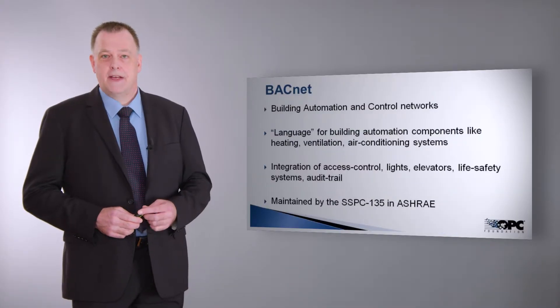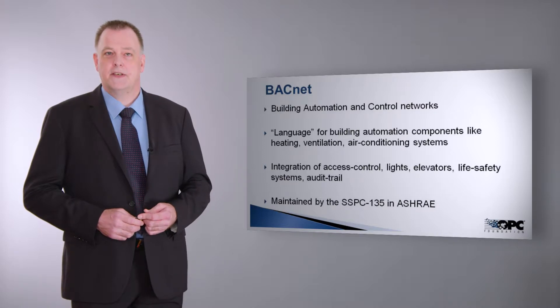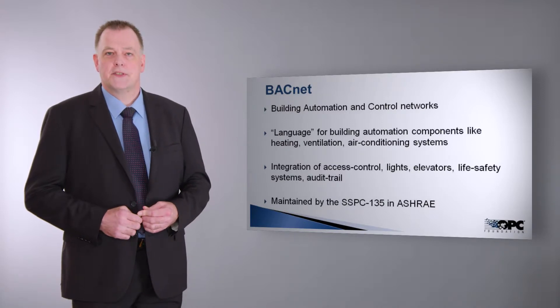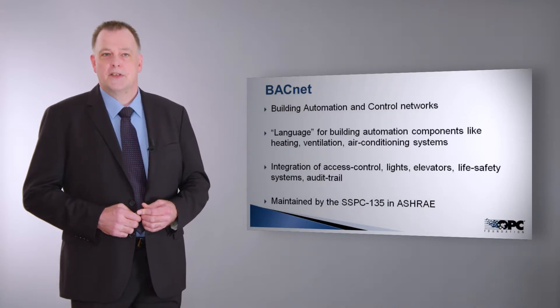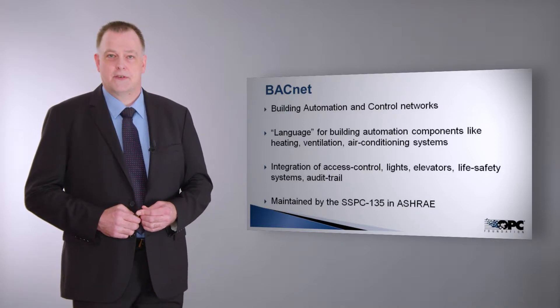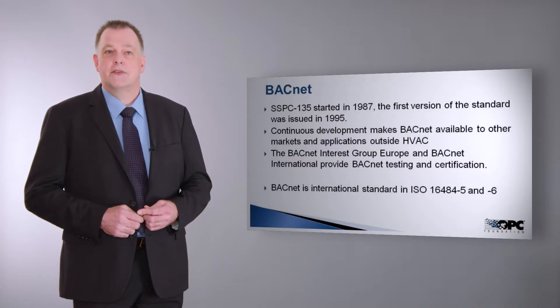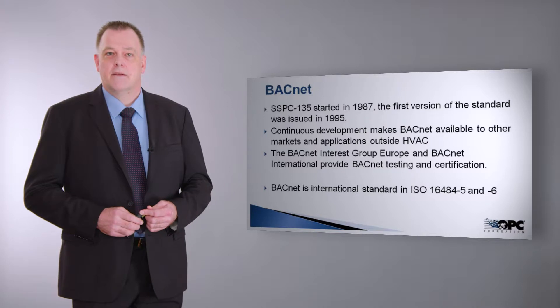A few words about BACnet. BACnet was founded in 1987 by the American Society of Heating, Refrigerating and Air Conditioning Engineers, ASHRAE. BACnet is a language for building automation to present data from heating, ventilation, air conditioning systems, but of course also from systems like life safety alarms, audit trail systems, elevators, or access control systems. BACnet is maintained by ASHRAE in SSPC 135, also known as the BACnet Committee. SSPC 135 started in 1987 to specify the BACnet standard and BACnet is under continuous development by this association in an open working group.